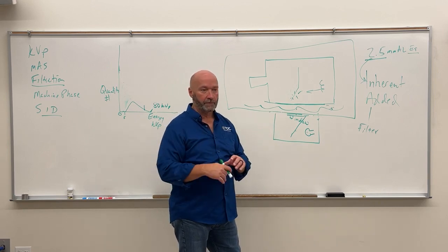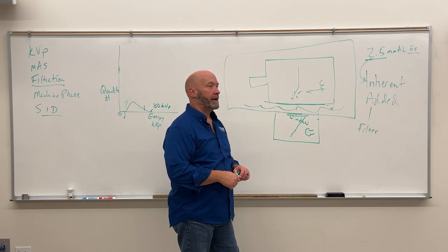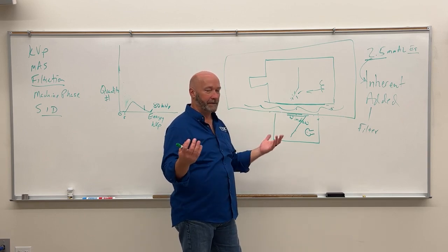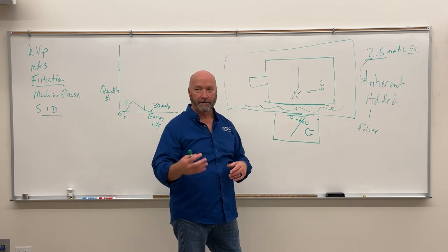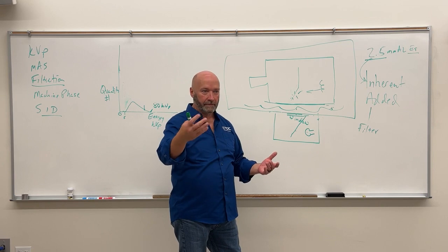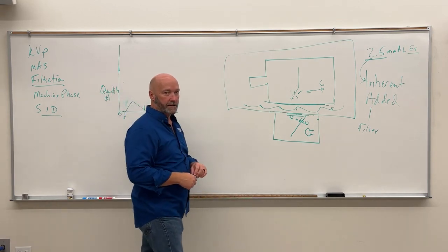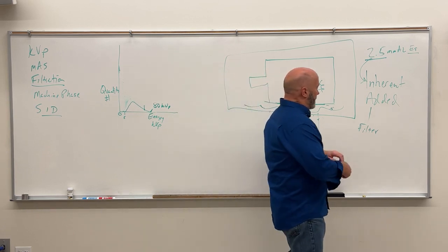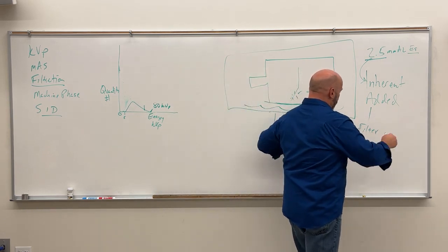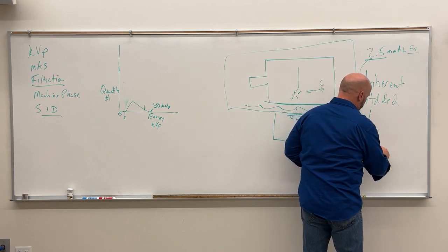They've got specific tubes for mammography. Possibly, probably not see it, but possibly if you're doing pediatric patients, you would want an x-ray beam that had fewer low energy x-ray photons. So those sort of things. But you've also got added filtration, which are compensating filters.